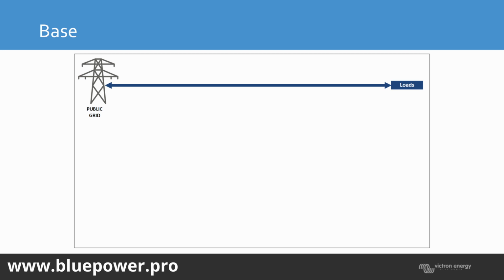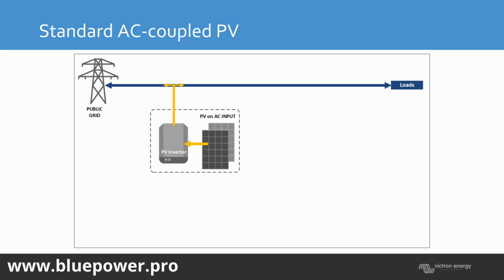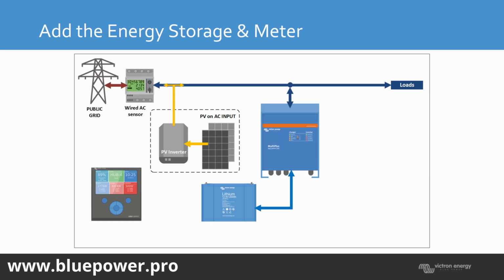So this is a basic ESCOM connection. Then you've got an AC coupled PV system. That's just a normal grid tie installation, saving power whenever there is electricity available to produce power. Next system we've got here is adding an energy meter to our grid tie PV system and a backup system. So what we can achieve this way is feed in limitation on our compatible PV inverter, and also utilize some of that PV power to charge our batteries on the backup system.